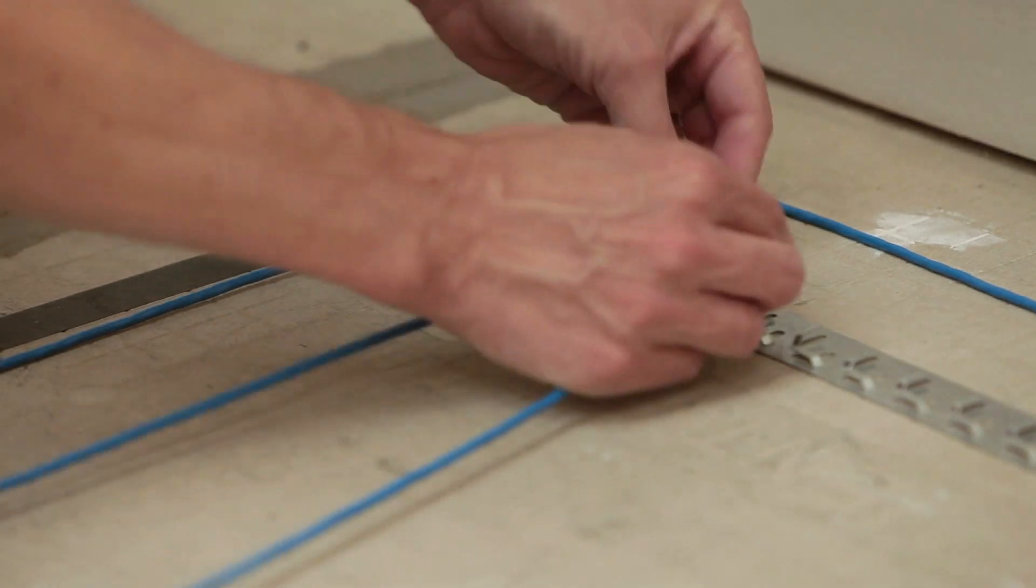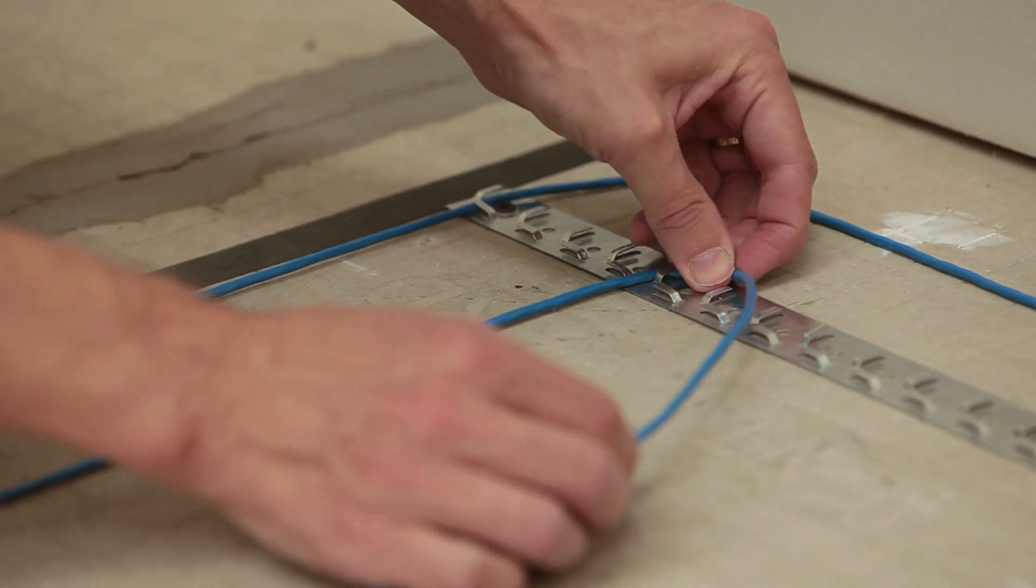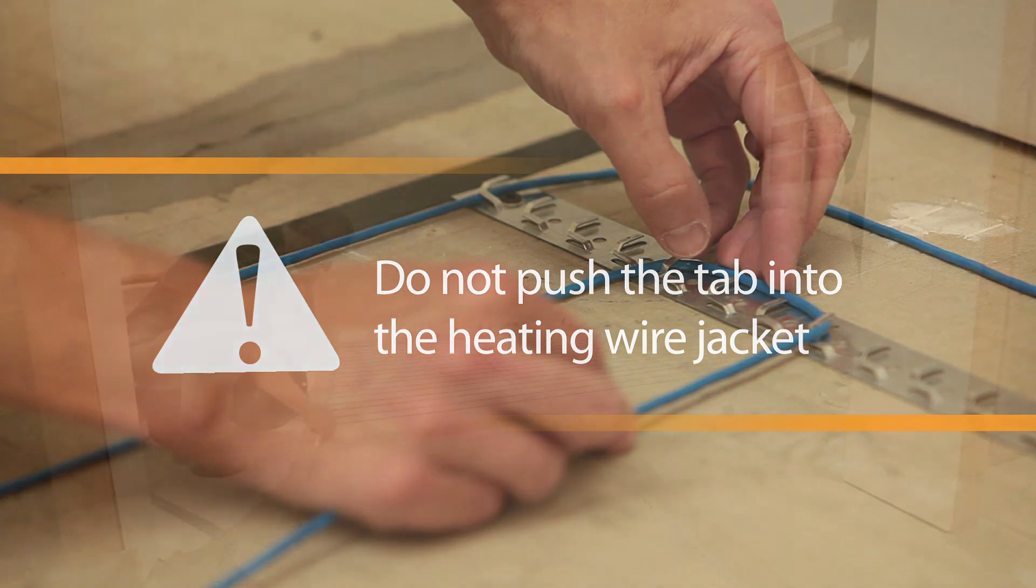Place the wire under the first tab. Bend each tab to secure the heating wire in place by hand. Do not use a hammer. Be careful not to push the tab into the heating wire jacket. Doing so may damage the wire.